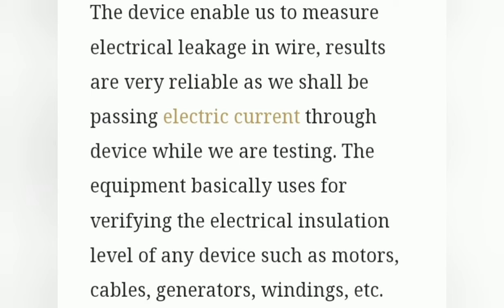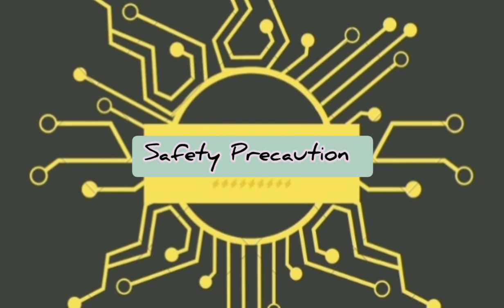The device enables us to measure electrical leakage in wire. Results are very reliable as we are passing electric current through the device while we are testing. The equipment is basically used for verifying the electrical insulation level of any device such as motors, cables, generators, windings, etc. Safety precaution: never touch the test leads while the handle is being cranked.